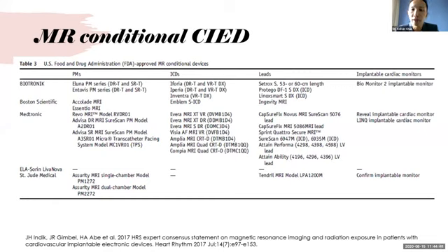Like for example, if we see the Abbott and St. Jude Medical devices, you see that there are no high voltage devices listed here, but actually if you check with them, they've all been MR conditional. Their newer range of ICDs and CRTs, including those from the Quadra series, are all approved for 1.5 Tesla full body MRI. Likewise for Boston Scientific, you see that only the subcutaneous ICD is listed here. But actually the newer series like Dynagen, Inogen, Charisma, are all approved for 1.5 Tesla full body MRI as well.